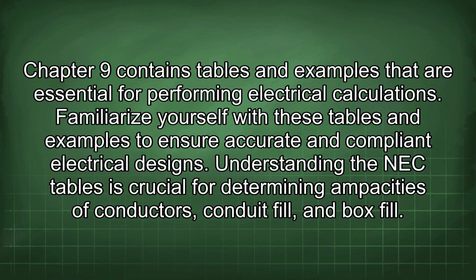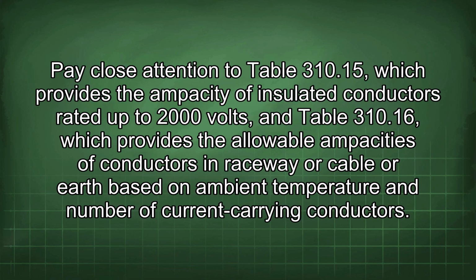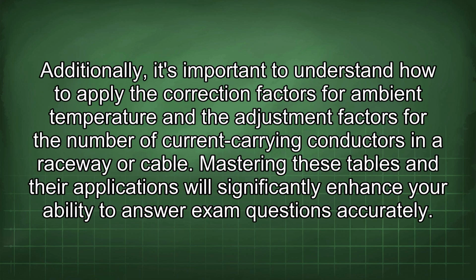Understanding the NEC tables is crucial for determining ampacities of conductors, conduit fill, and box fill. Pay close attention to Table 310.15, which provides the ampacity of insulated conductors rated up to 2000 volts, and Table 310.16, which provides the allowable ampacities of conductors in raceway or cable or earth based on ambient temperature and number of current carrying conductors. Additionally, it's important to understand how to apply the correction factors for ambient temperature and the adjustment factors for the number of current carrying conductors in a raceway or cable. Mastering these tables and their applications will significantly enhance your ability to answer exam questions accurately.